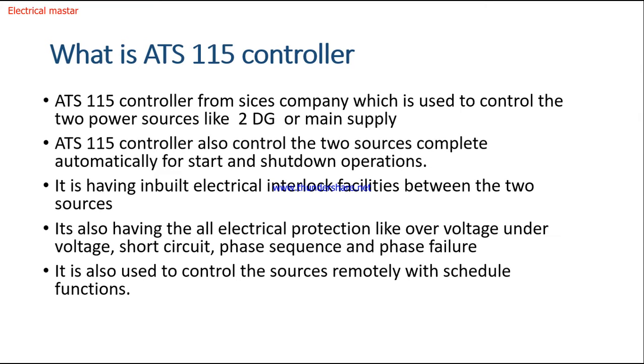And the ATS 115 controller also controls these two sources completely automatically for start and shutdown operation. It means once you connect the two sources and put it in auto mode, it will automatically complete the start and stop operation like AMF or ATS control. If main supply is available, it will keep the DG off. If main supply is off, it will start the DG automatically. Once the main supply comes back, it will automatically shut down the DG. So the complete operation is done by this ATS 115 controller.